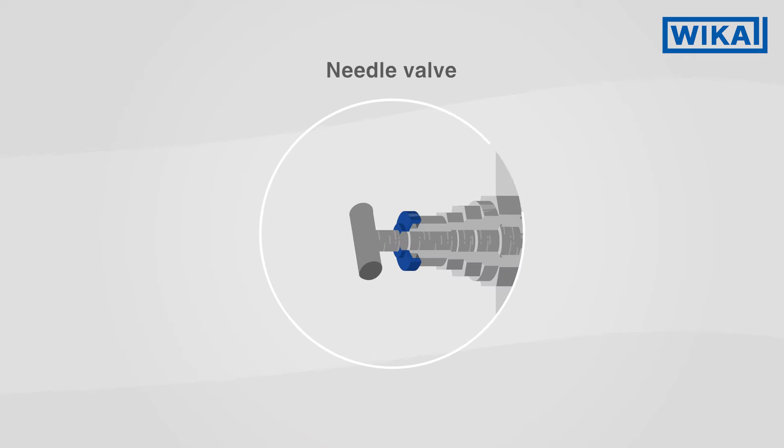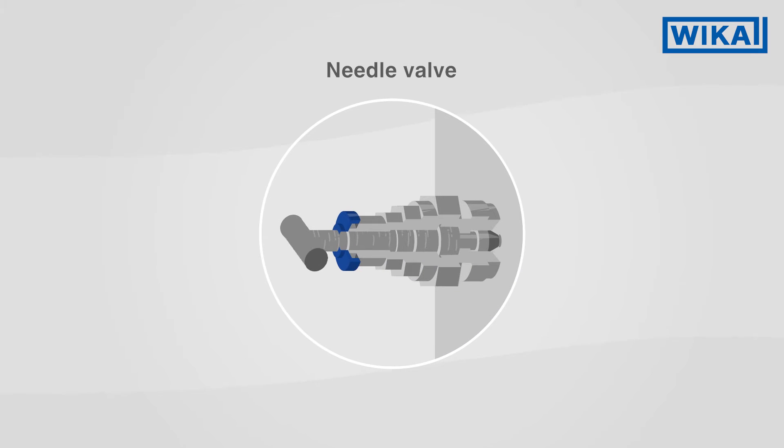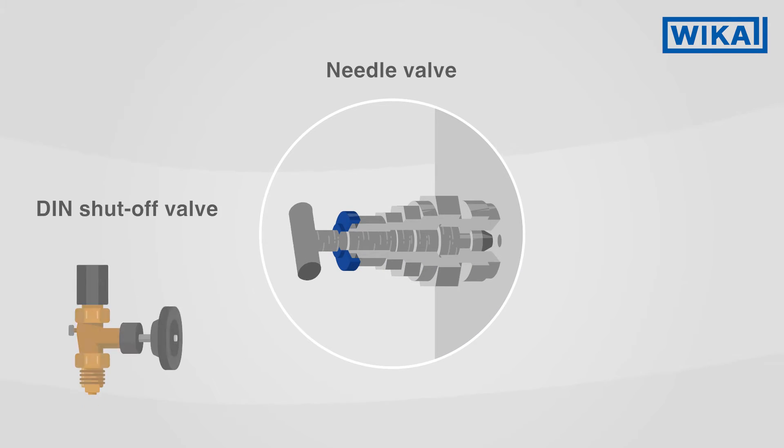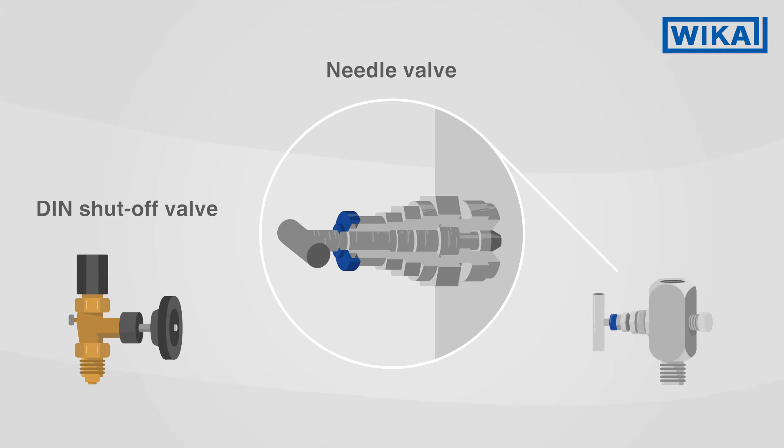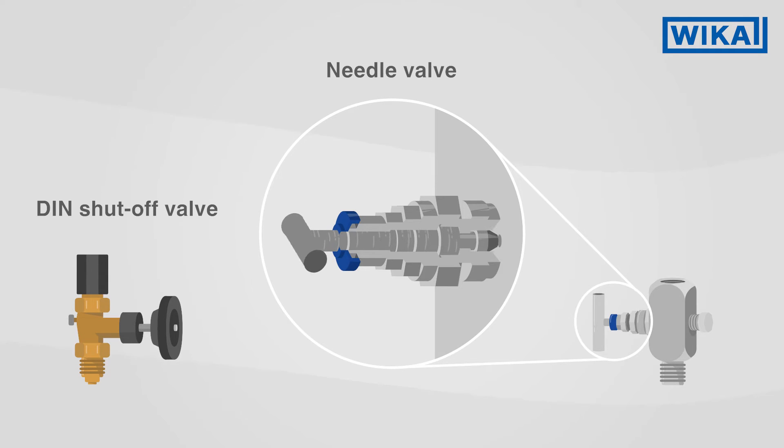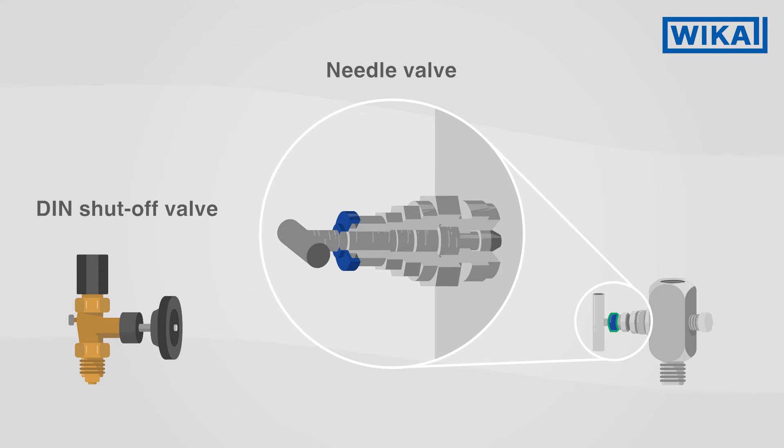With a needle valve, a needle shuts off the process. In Germany and Europe, the DIN shut-off valve with handwheel is common, while the needle valve is used worldwide. The non-rotating spindle tips mean low wear and tear and allow the valve to operate very smoothly.